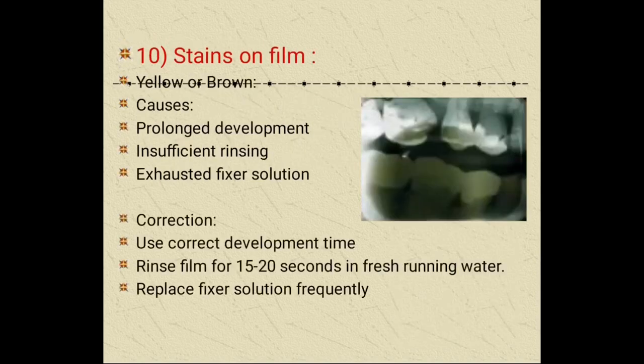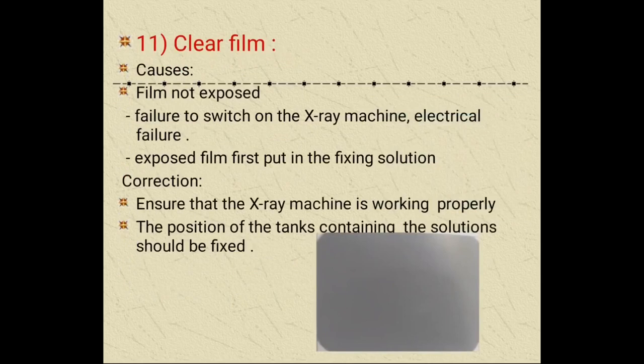Stains on the film appear as yellow or brown stains, caused by prolonged development, insufficient rinsing, or exhausted fixer solution. Correct by using the correct development time, rinsing the film for 15 to 20 seconds in fresh running water, and replacing the fixer solution frequently. A clear film — where nothing appears — means the film was not exposed, due to failure to switch on the x-ray machine, electrical failure, or the exposed film being put in the fixing solution before the developing solution. Ensure the x-ray machine is working and the tanks are positioned correctly: developer first, then washer, then fixer.